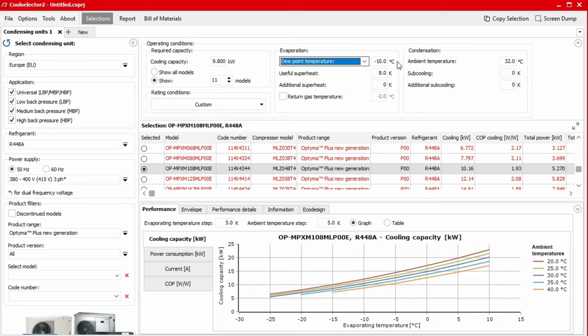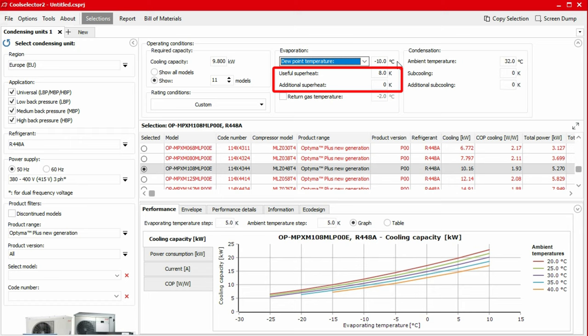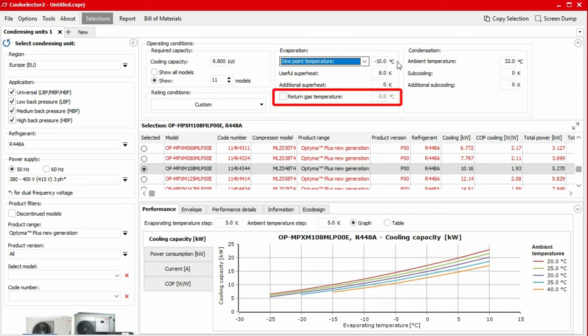However, total superheat is more important as a higher superheat at the end of the suction line, when the gas enters the compressor, results in a higher volumetric flow rate in the compressor and also a higher discharge temperature. We can specify the superheat by specifying useful superheat and the additional superheat, or alternatively, if we have short suction lines in the system, we can simply select the return gas temperature.